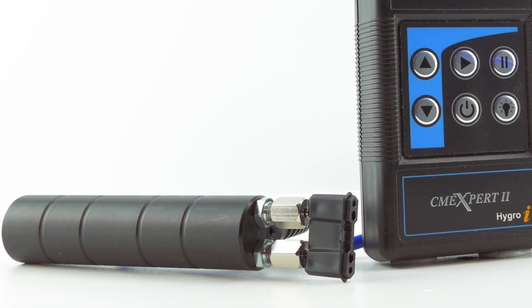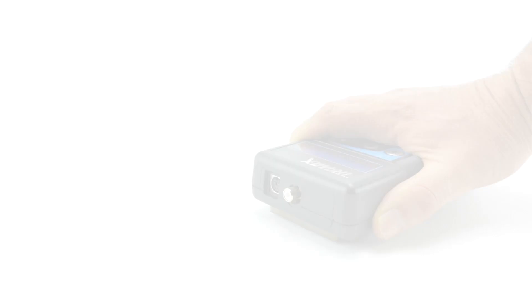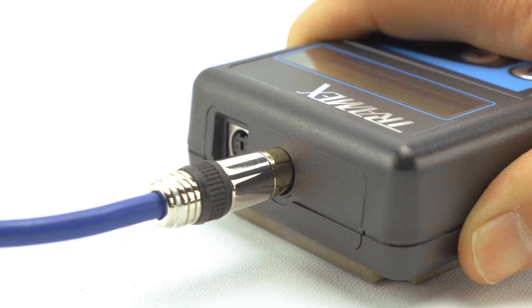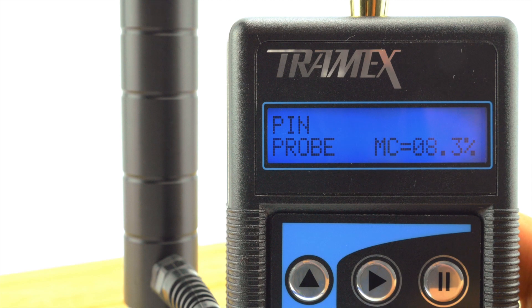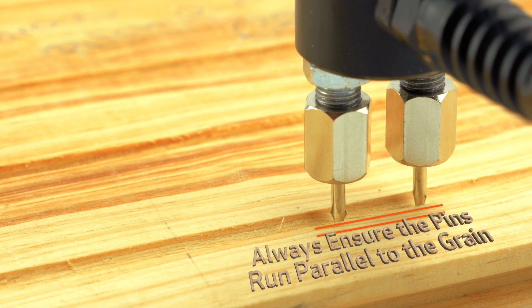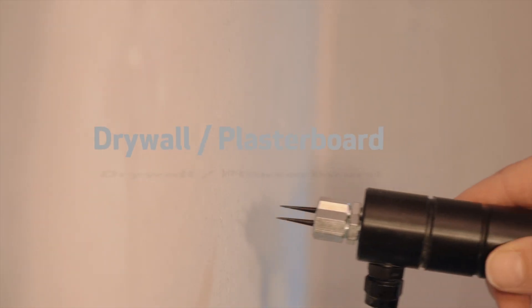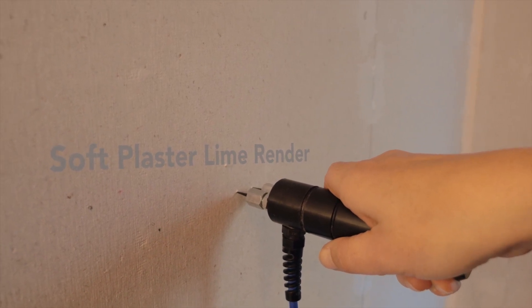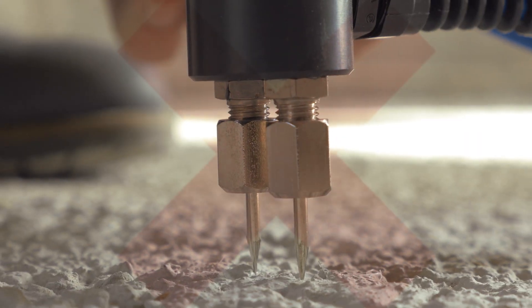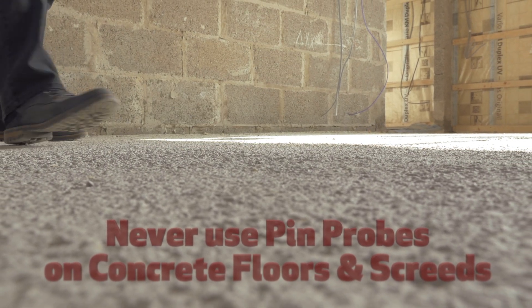The CME X2 can be used to test wood with a pin type attachment for resistance measurement. To take resistance measurements with the pin probe, simply plug the probe attachment into the top of the meter and press the play button until the screen reads "pin probe". Then fully press the pins into the wood sample to achieve the most accurate measurement. Always ensure the pins run parallel to the grain. The pin probe function may also be used with other materials such as drywall, plasterboard, or soft plaster lime render for comparative readings. This type of measurement is sometimes referred to as WME or wood moisture equivalent. Tramex would never recommend the use of pin type measurements for concrete floors and screeds, as the pins cannot penetrate the surface and the reading can be greatly affected by ambient humidity.